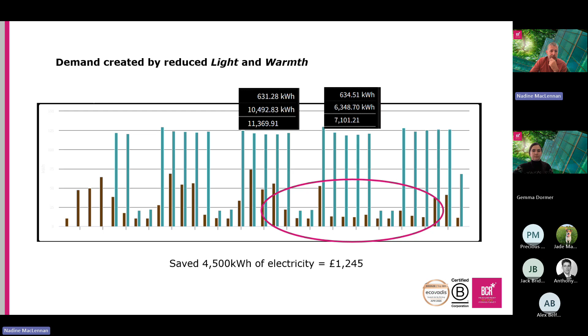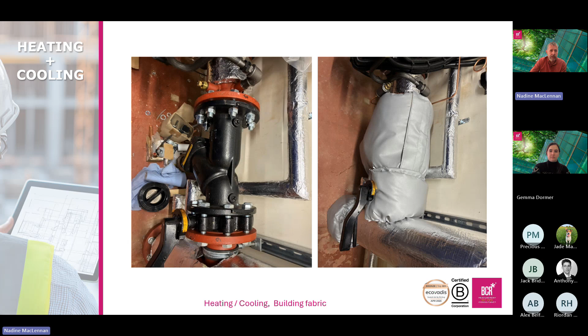First thing is go and stand in the boiler room. The boiler room in most sites is a wonderful place to be on a cold winter's day, because it's lovely and roasty and toasty. The reason being is because you have these sorts of things, which is a manifold on a heating system. It doesn't really matter what it is, but when you put a thermal camera on it, it's absolutely glowing - you don't want to touch that, it's pretty hot. What it should look like is different, because the heat coming out of that manifold is heating a boiler room, which doesn't need heating, not your offices. So it's literally radiating money and waste.